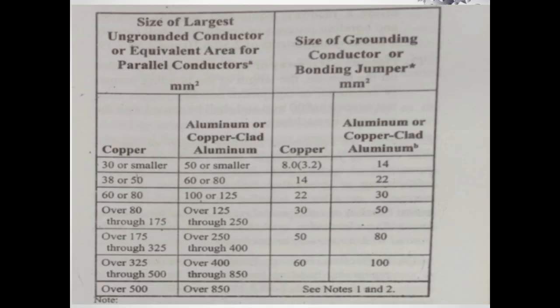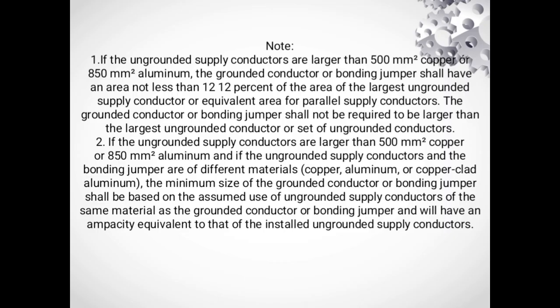Copper: 8.0 or 3.2, 14, 22, 30, 50, 60. Aluminum or copper-clad aluminum: 14, 22, 30, 50, 80, or 100. Note 1: If the ungrounded supply conductors are larger than 500 mm squared copper or 850 mm squared aluminum, the grounded conductor or bonding jumper shall have an area not less than 12 1/2 percent of the area of the largest ungrounded supply conductors or equivalent area for parallel supply conductors.